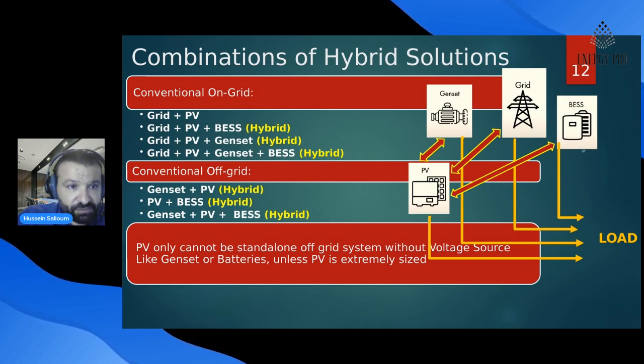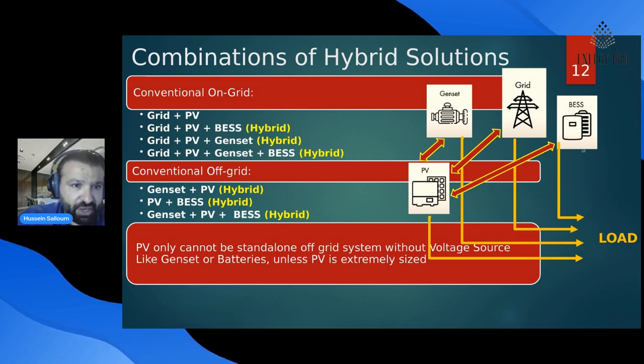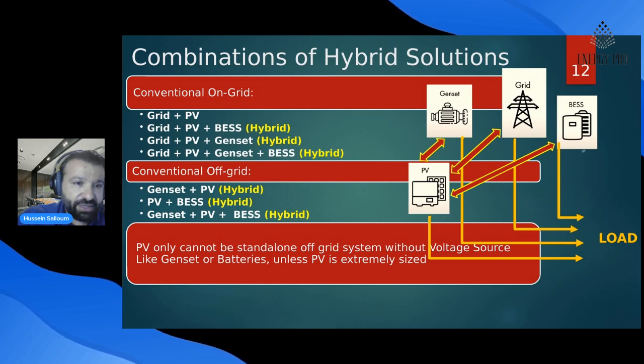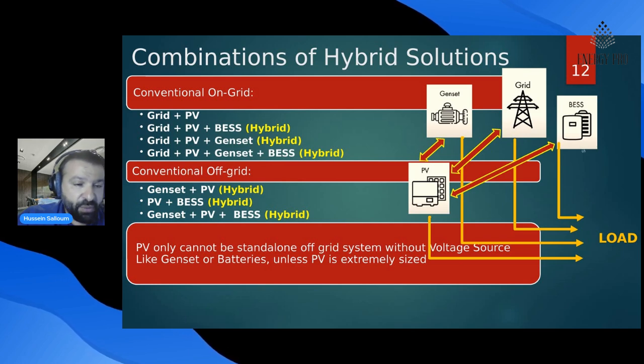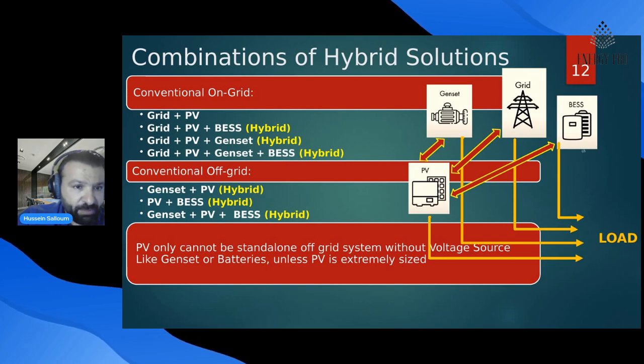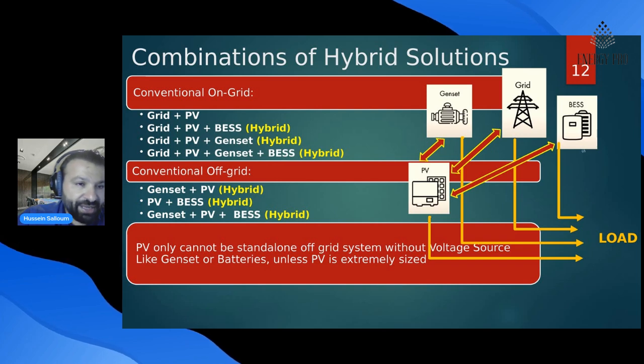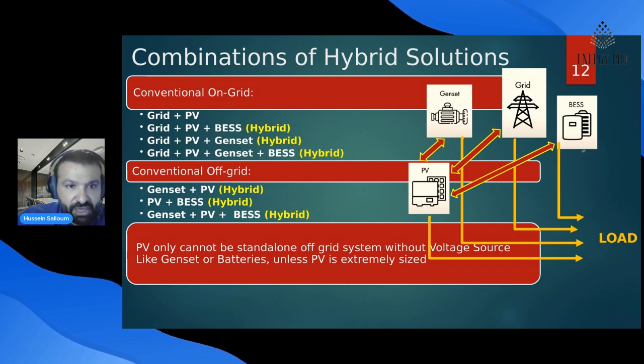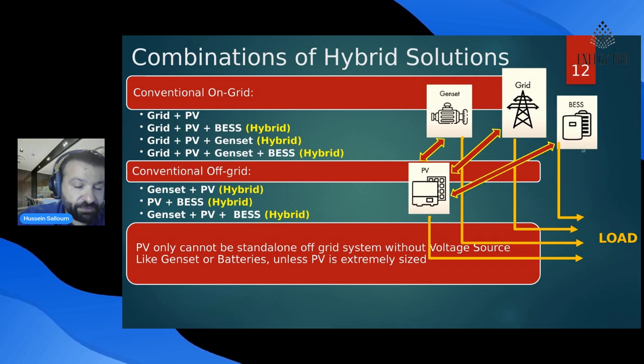On the other hand, we have the off-grid combinations. We will have the generator and the PV, as in the off-grid without the grid, so it will form a hybrid solution. It can also be a PV with the battery only, and that will also be a hybrid solution. And it can be a generator with a PV with an energy storage system, and that will form a tri-source hybrid solution. But if we have only a PV, it cannot be used as a standalone off-grid system without any voltage source, whether it be the grid forming inverter or a battery or a generator.